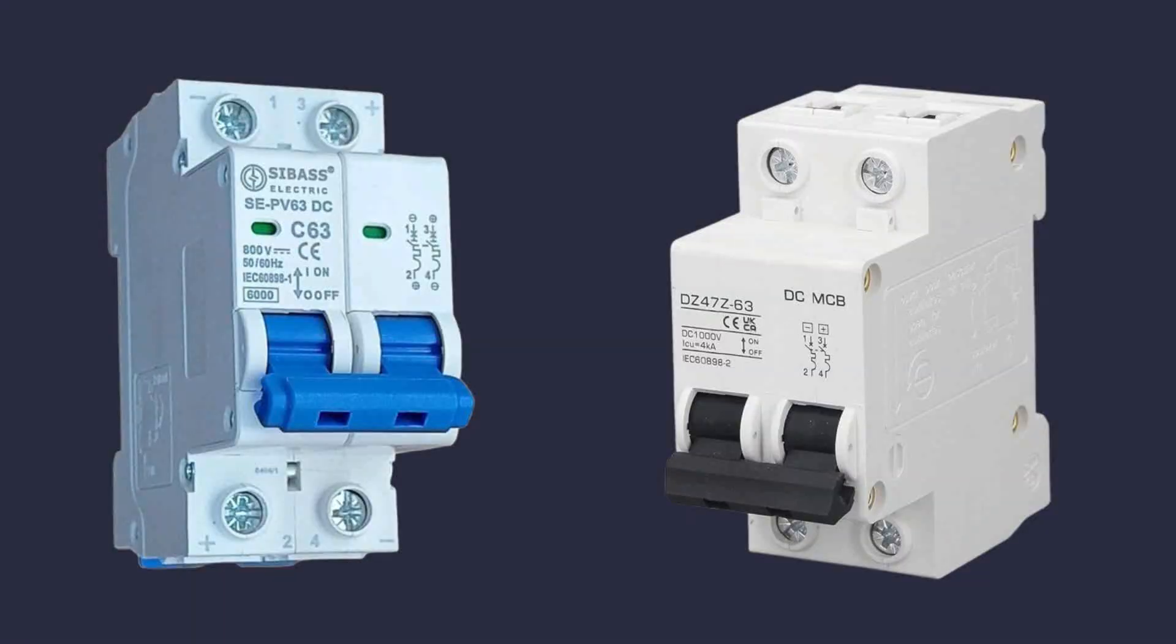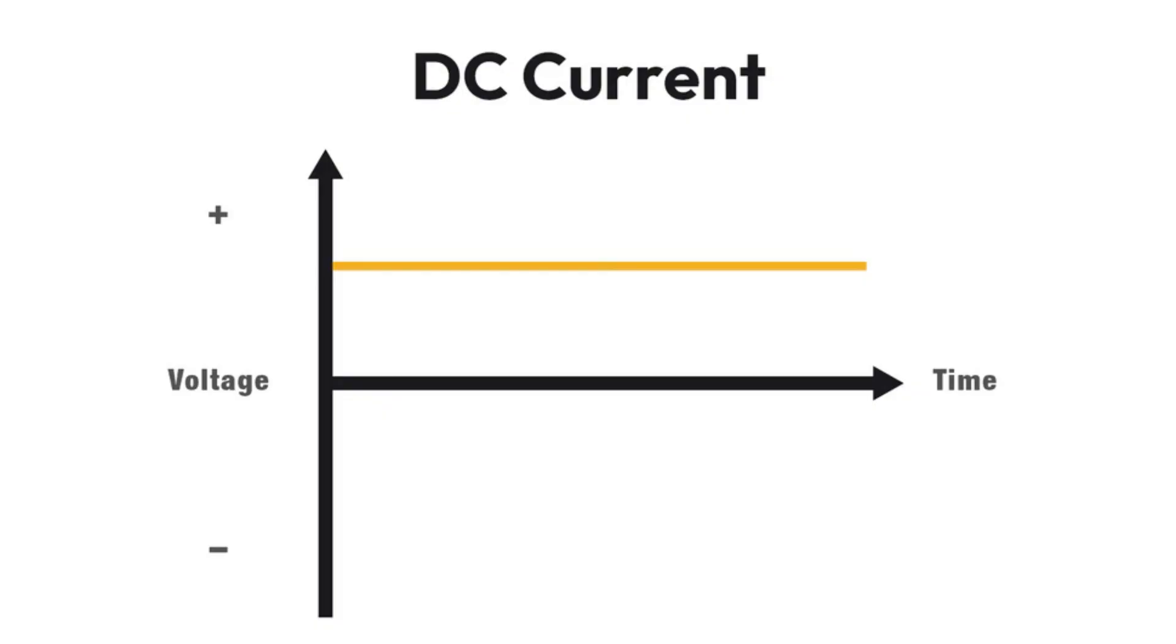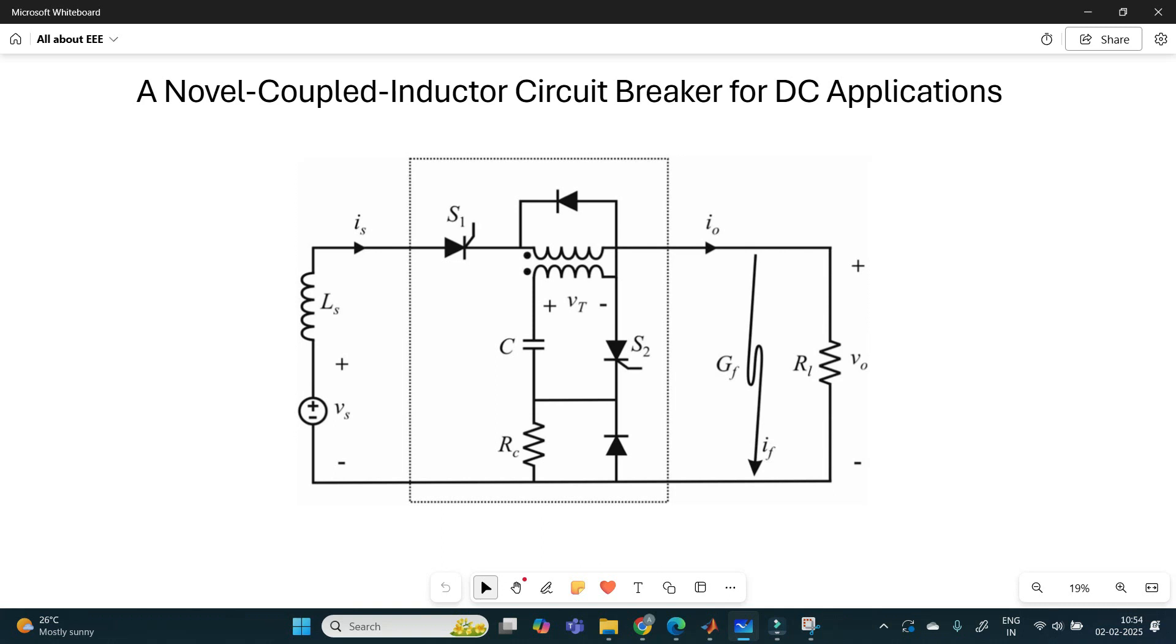However, when it comes to DC circuit breakers, many designs are still in experimental phase. The main limitation is that interrupting a current which does not have zero crossing will sustain an arc. This video introduces a new type of DC circuit breaker.